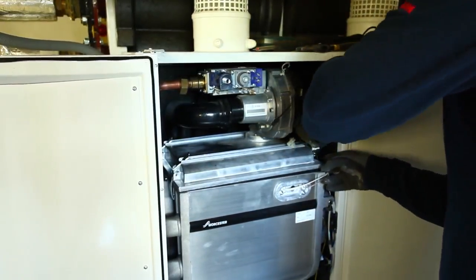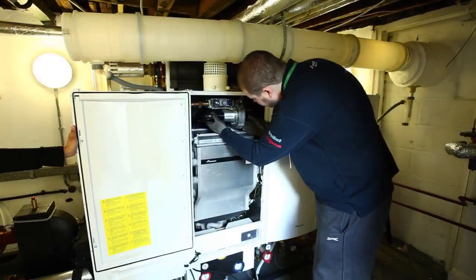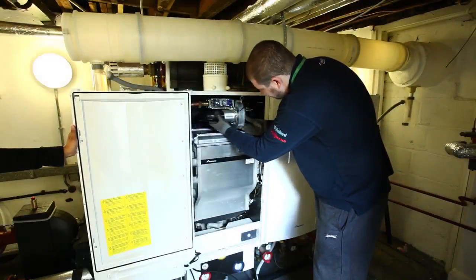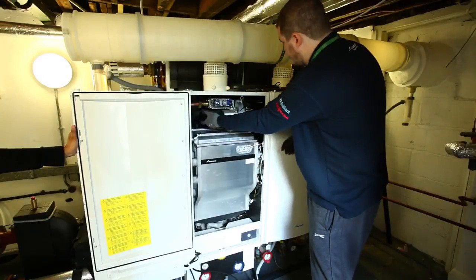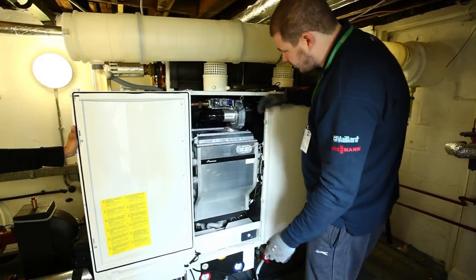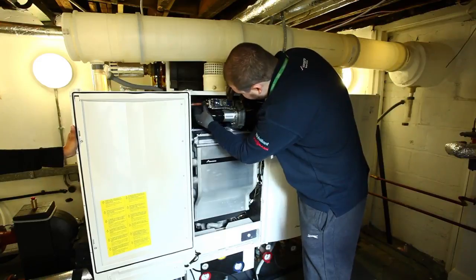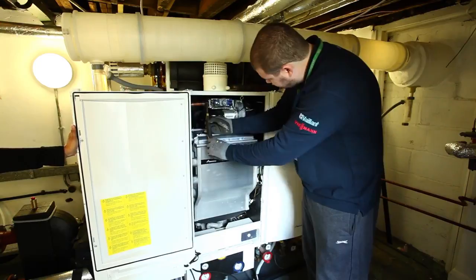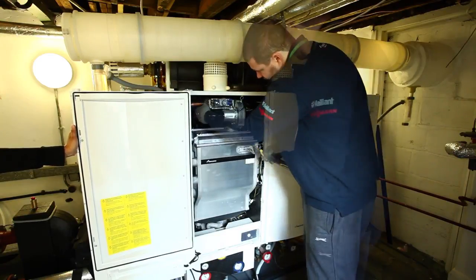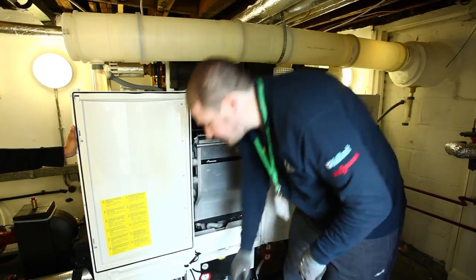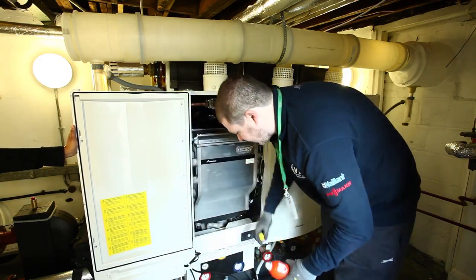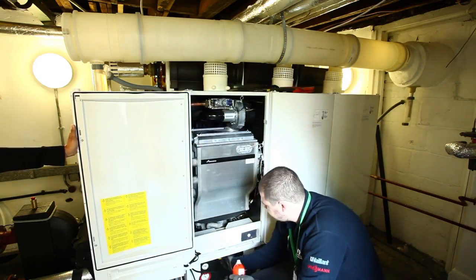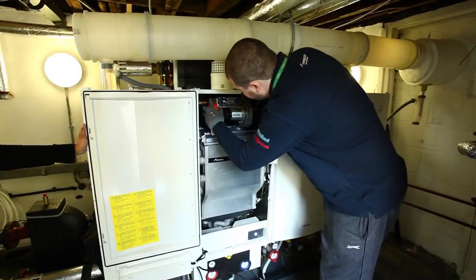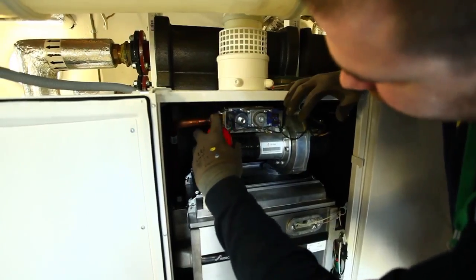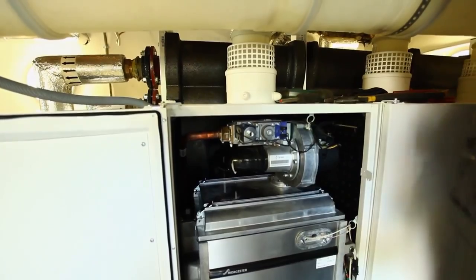All the way around on the 4 lugs. We reconnect the air intake back onto the fan. This makes sure that all dust doesn't go into the heat exchanger as much as possible. We then reconnect the gas pipe to the gas valve. Then we usually use a 1/4 or 1/8 of a turn to tighten it up. Then we test it with leak detection spray. We turn the gas on again. Then we just spray our broken connection, making sure there's no bubbles indicating a gas leak.